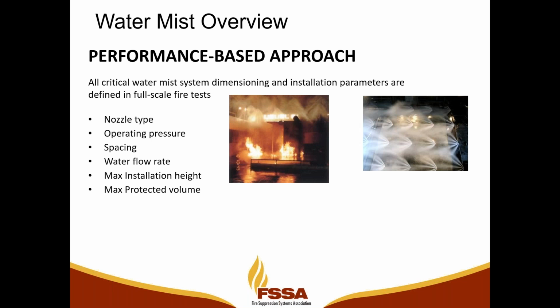When you're dealing with water mist systems, they are performance-based. So we can't necessarily apply them in a prescriptive manner just because something might be similar. They have to specifically be performance-based tested, and in that testing, we have to be able to define nozzle type, operating pressure, spacing, water flow rate, max installation height, and max protected volume for that system.